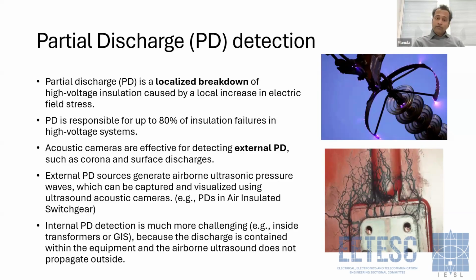And if we consider these acoustic cameras for partial discharge detection, we can detect partial discharges by using acoustic cameras whenever there are external PDs. There might be internal PDs as well as external PDs on these insulators. When it comes to external PDs, for example corona discharges and surface discharges, they can be easily detected with ultrasound cameras. As an example, if you take air insulated switchgear or outdoor high voltage switchgear, most of these partial discharges happen externally, either as corona or surface discharges. On the other hand, if you take a transformer or GIS, those are enclosed high voltage equipment, so they would have internal partial discharges.